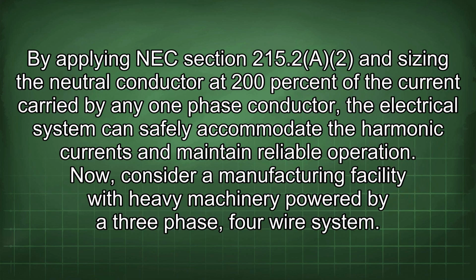By applying NEC section 215.2 and sizing the neutral conductor at 200% of the current carried by any one-phase conductor, the electrical system can safely accommodate the harmonic currents and maintain reliable operation.